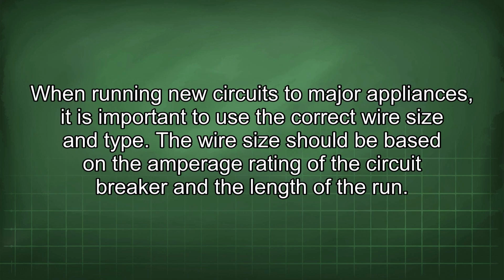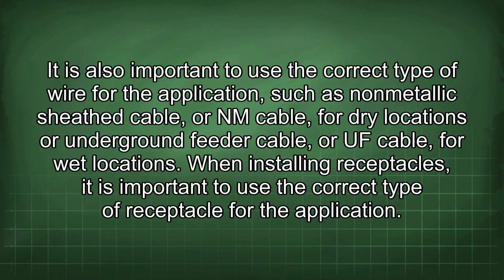When running new circuits to major appliances, it is important to use the correct wire size and type. The wire size should be based on the amperage rating of the circuit breaker and the length of the run. It is also important to use the correct type of wire for the application, such as non-metallic sheath cable or NM cable for dry locations, or underground feeder cable or UF cable for wet locations.